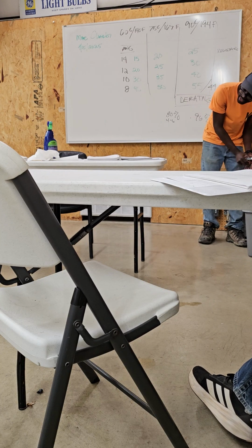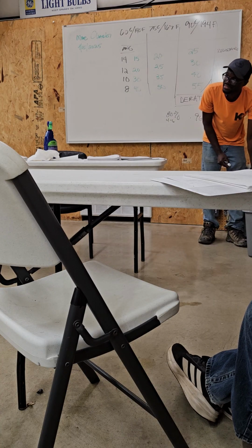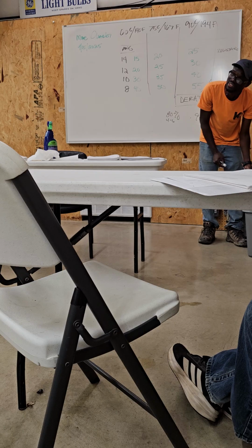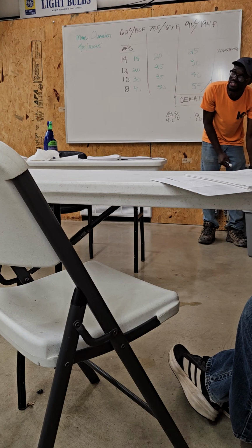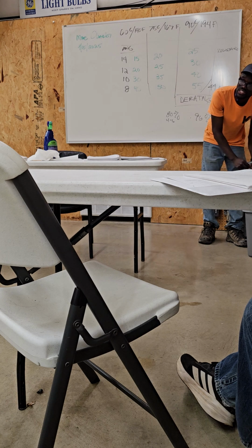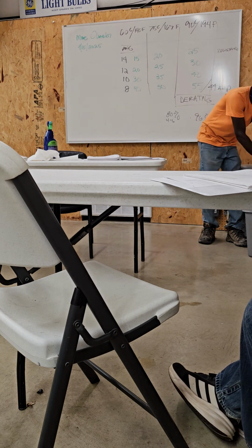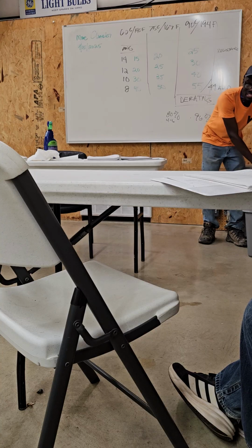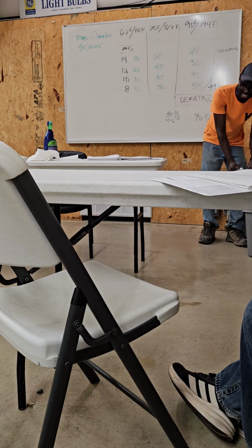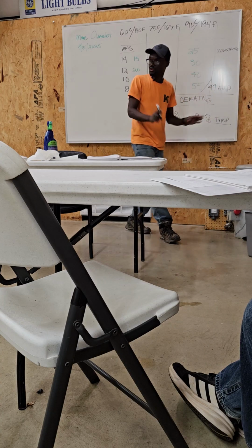That's the reason why, I'm gonna tell you guys, you do not strip those things and put them inside flexes. I know some of you guys do. You're not supposed to do that because there's a different jacket that goes on that one. The jacket on this one is not the same jacket that is on a THWN. The THWN is meant to go outside. This guy is not meant to go outside. This guy's supposed to stay inside. Unless you can look somewhere in there and see it's a THWN, but that's a different story.